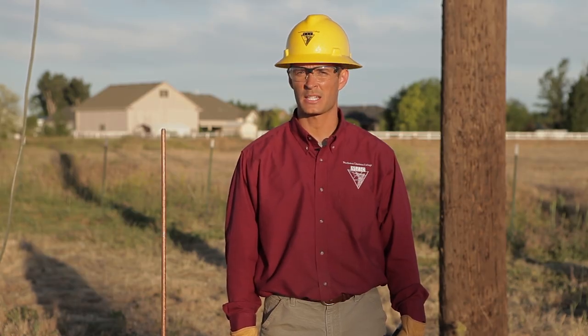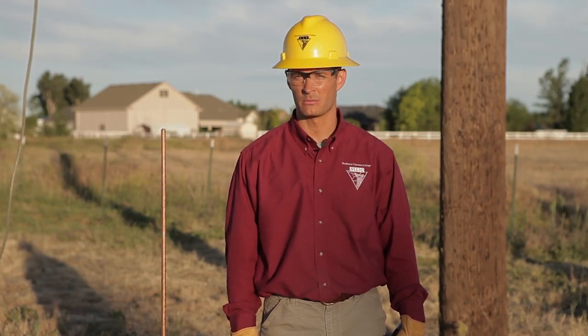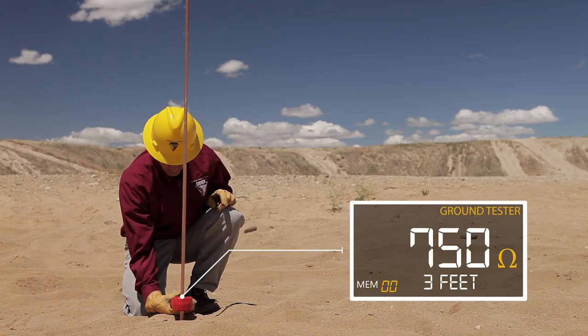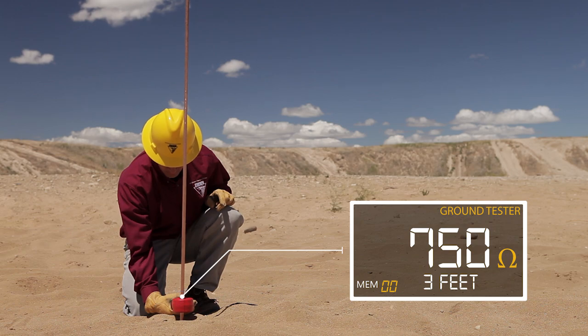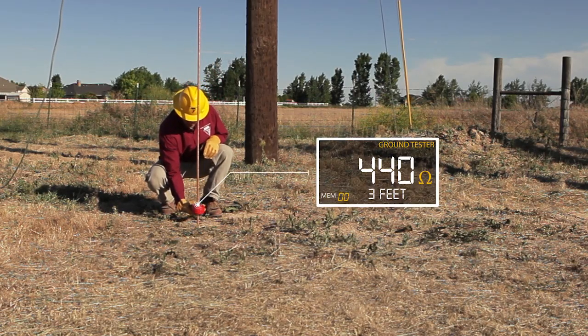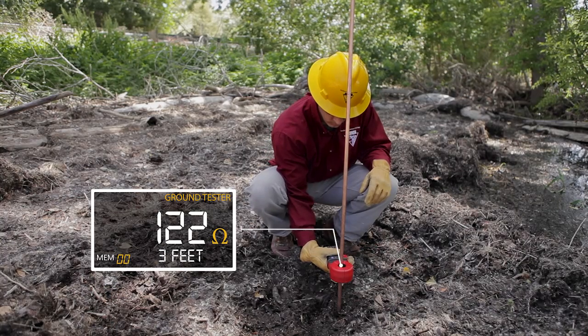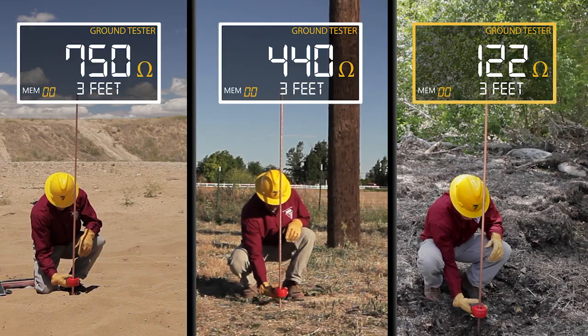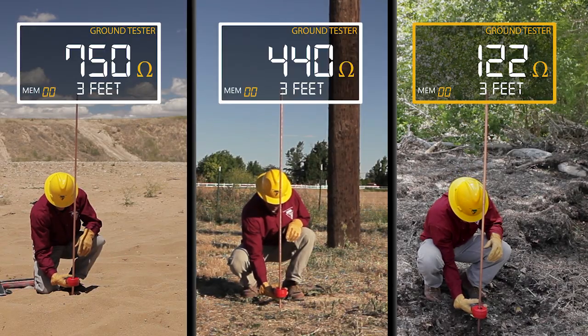Resistance is also affected by the type of soil the ground rod is driven into. I drove a ground rod three feet in the sandy soil and got a resistance of 750 ohms, which is more than the ground rod driven three feet in the dirt that had a resistance of 440 ohms. I also tested the resistance in swampy soil at the same depth and got a resistance of 122 ohms. So of the three soils tested, the swampy soil had the best grounding source.